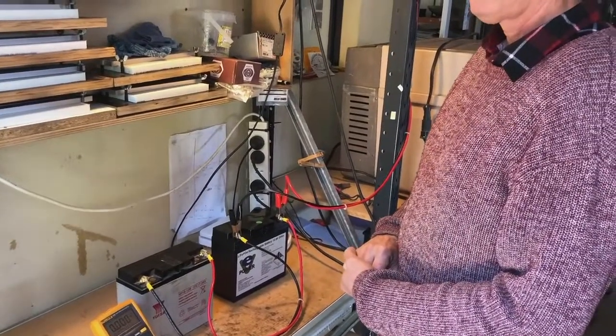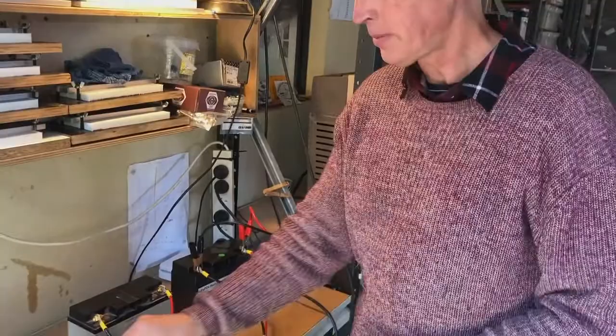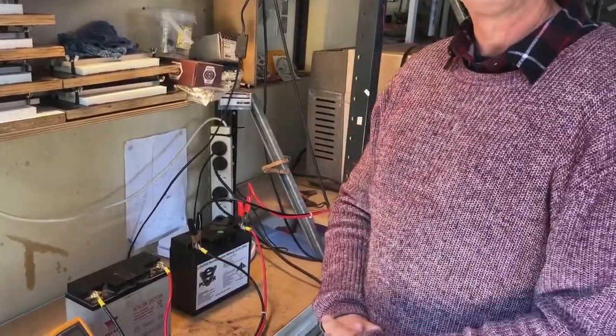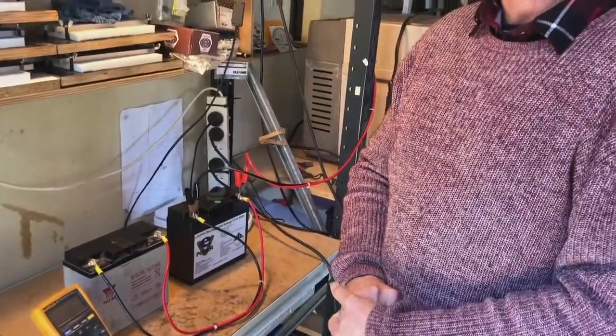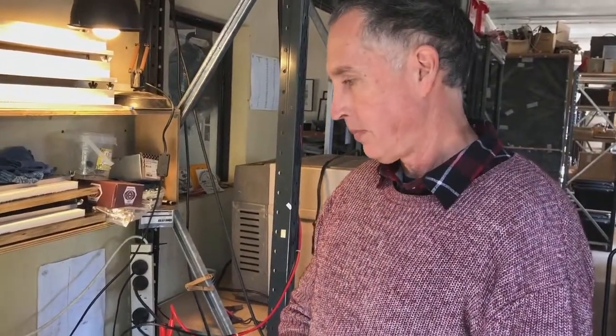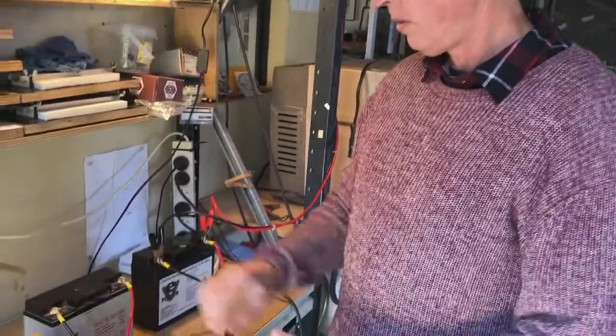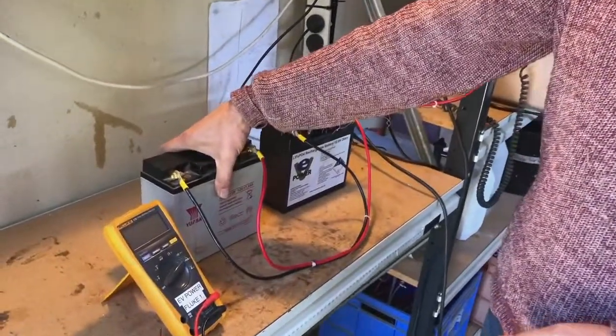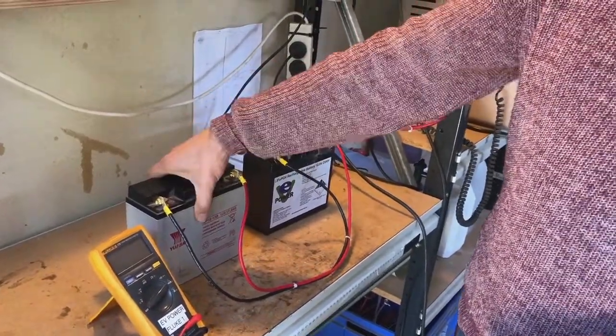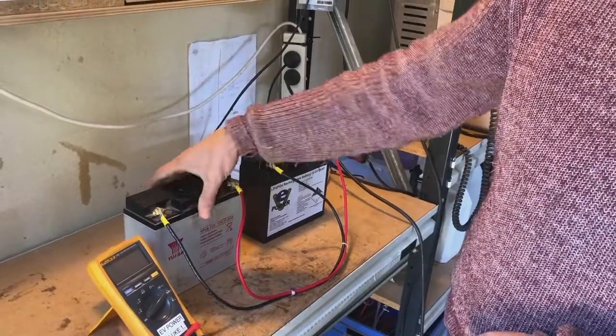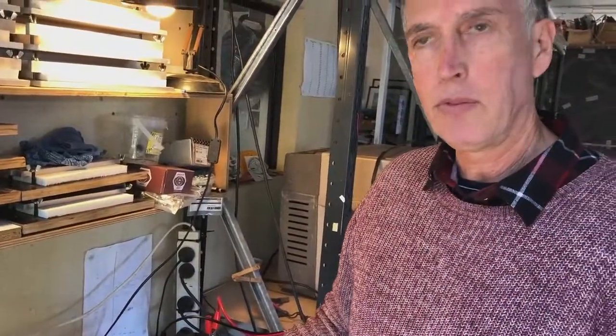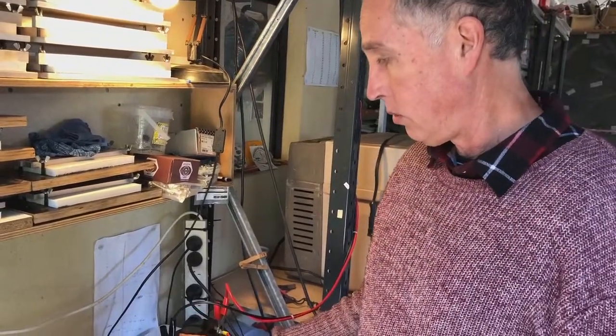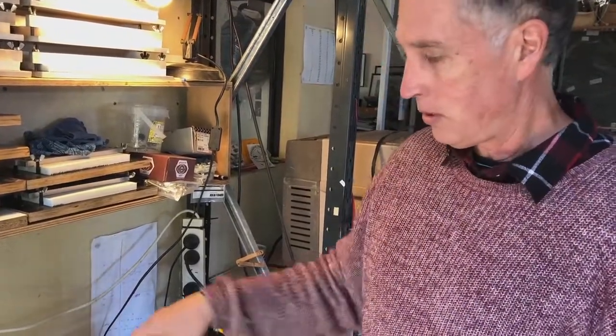What do you think might happen if the lead acid had a weak cell or failed, under those conditions? Good point. The general failure mode of a lead acid battery is it'll lose a cell—one cell might go to 0 volts, and the battery voltage will drop back to 10 volts, and if you had a good lithium battery, that would discharge into it.